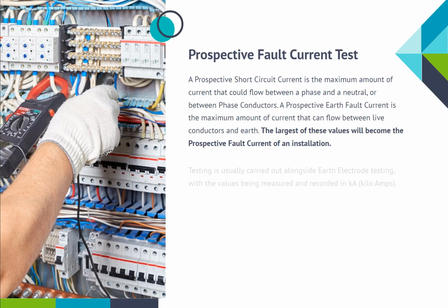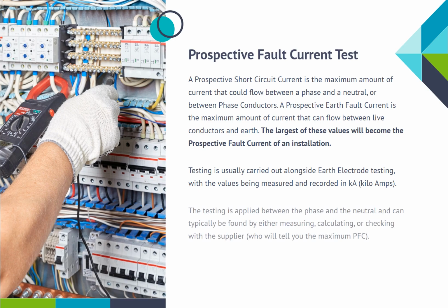Prospective fault current test. A prospective short-circuit current is the maximum amount of current that could flow between a phase and a neutral, or between phase conductors. A prospective earth fault current is the maximum amount of current that can flow between live conductors and earth. The largest of these values will become the prospective fault current of an installation.